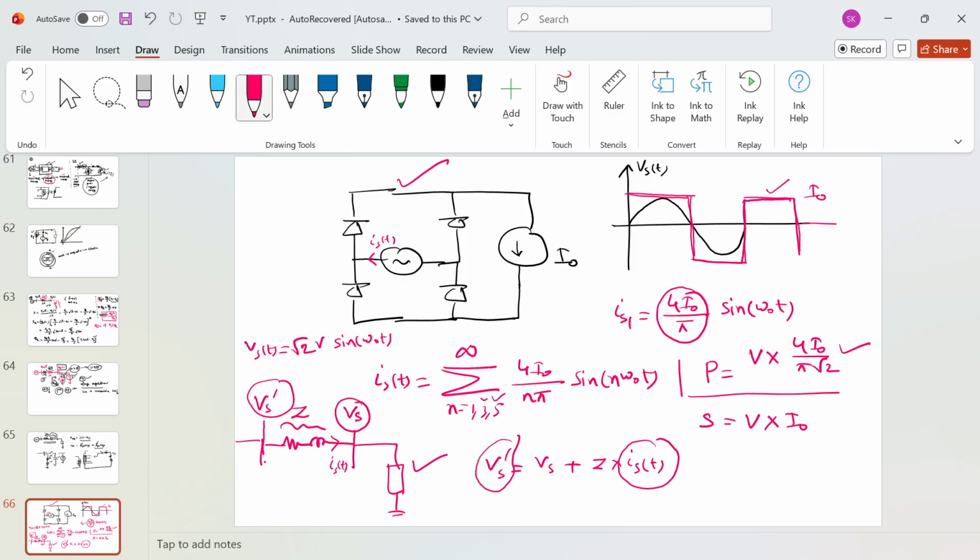So if I have another load connected over here, say any RL type of load, the performance of this load will deteriorate. Because of the non-linear load, I am getting non-sinusoidal voltage in the buses that are connected, or that are in the vicinity of this particular bus.